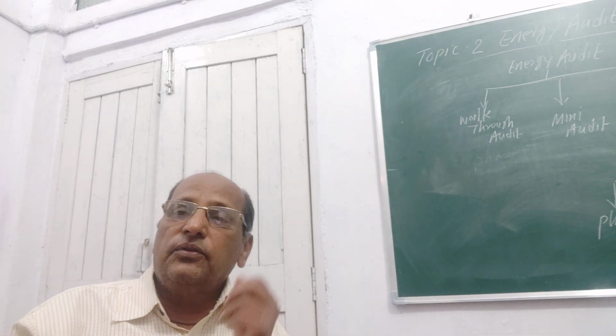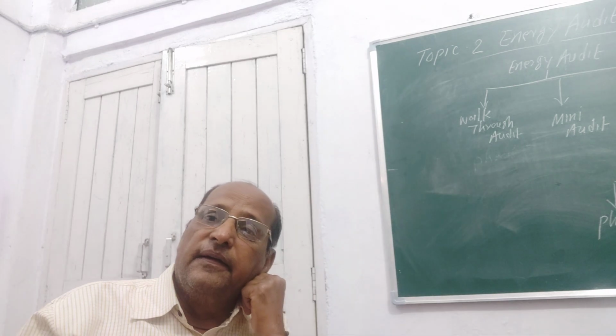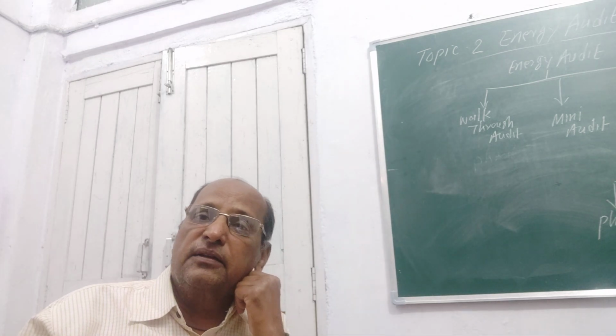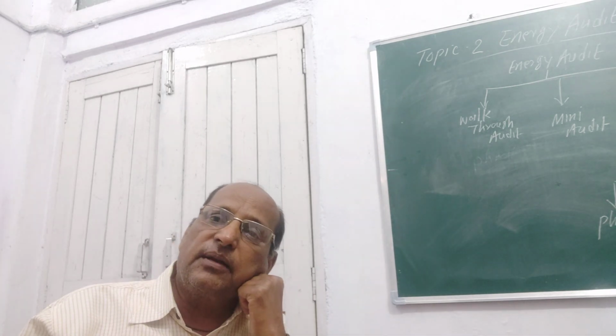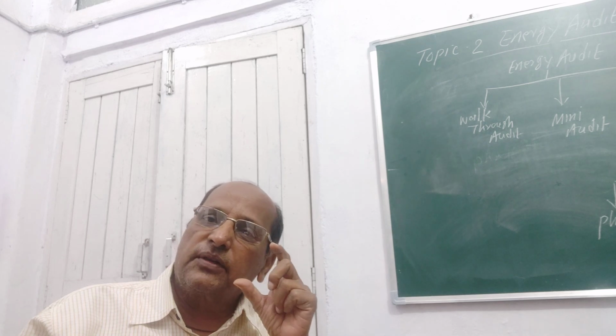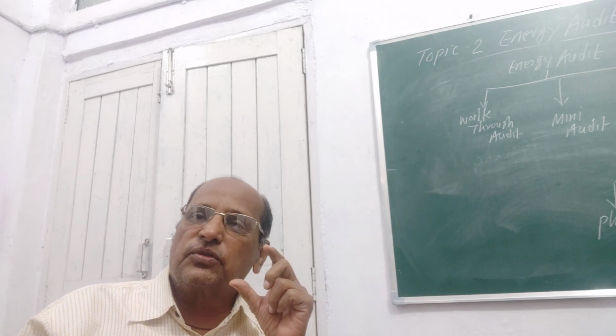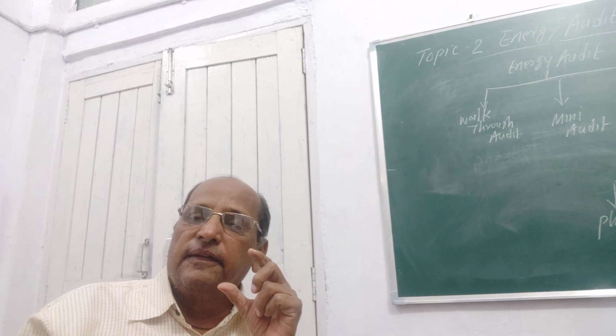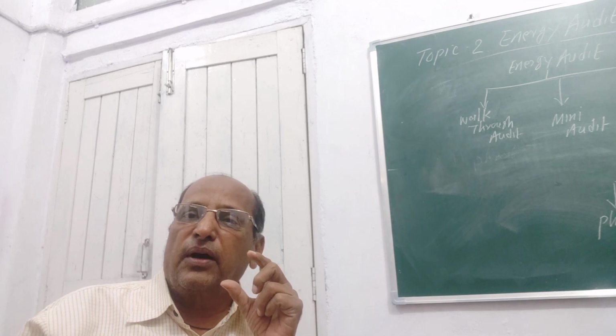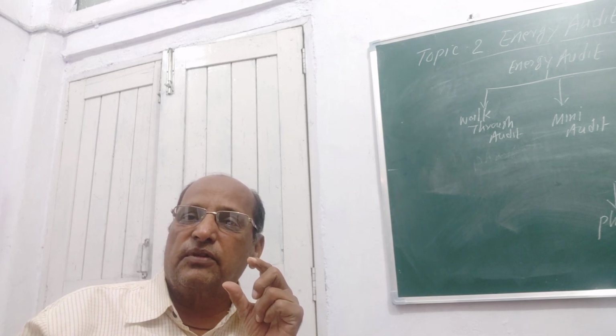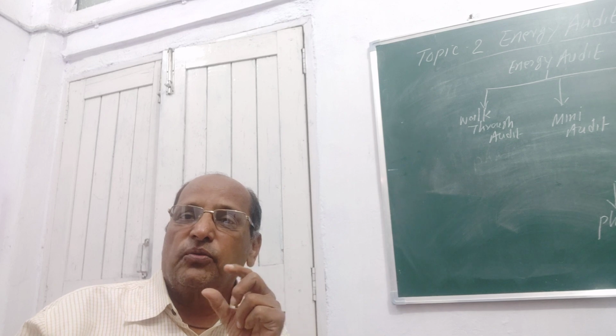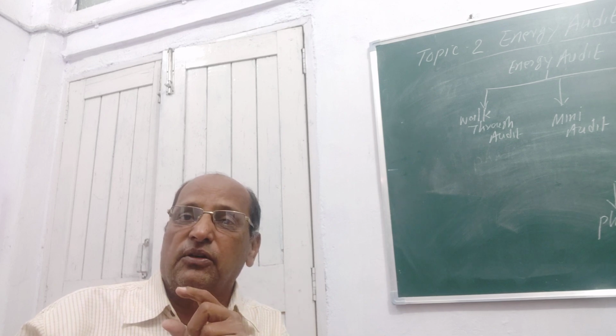You have to apply the capacitor bank to improve the power factor of that machine on that particular supply or distribution point, so that this machine, which is operating on 0.67 power factor, which is very poor as compared to 0.95 which is actually required.